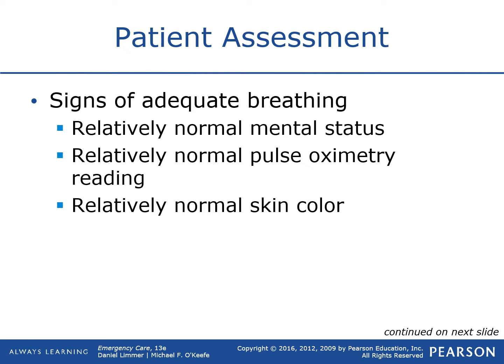There's a few issues that come with pulse oximetry. One of which is a lot of times you don't get an adequate reading. If someone has fingernail polish on, it's hard to shine that light through a finger and get an adequate reading. If someone's hands are cold, so they don't have adequate blood flow to their actual hands, then you aren't going to be getting an adequate reading. If you have any other thing on a finger, like dirt, sometimes that will alter the reading.